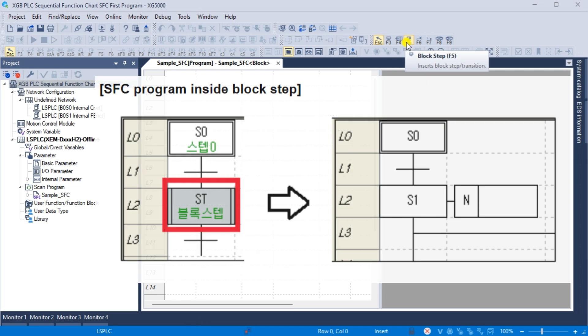Block step F5: when the block step is activated, the specified SFC sequential function chart program within the block is executed. Only SFC programs are permitted; LD ladder diagram or ST structured text programs cannot be included. It is important to note that actions cannot be linked to block steps. When the block step is deactivated, the SFC program running within the block is also deactivated.